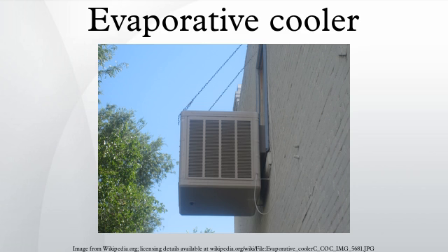Because the cooling air originates outside the building, one or more large vents must exist to allow air to move from inside to outside. Air should only be allowed to pass once through the system, or the cooling effect will decrease. This is due to the air reaching the saturation point. Often 15 or so air changes per hour occur in spaces served by evaporative coolers, a relatively high rate of air exchange.